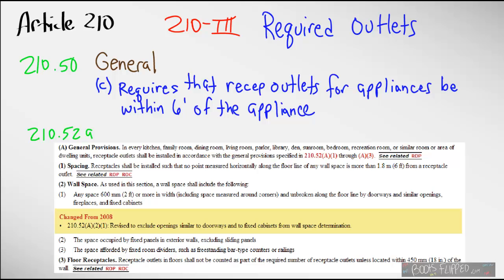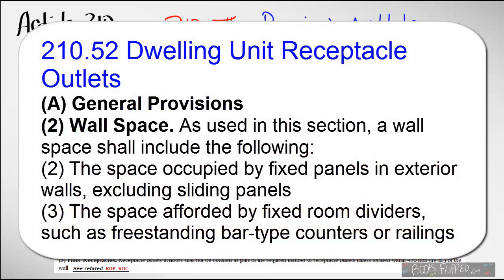Also, this code article lets us know that if there's a fixed panel on the exterior wall, that is included in wall space. Where that comes into play is if you have a French door that has one side that doesn't open, the side that doesn't open is counted as part of the wall. If you have a sliding glass door, the side that doesn't open is counted as part of the wall. The rest of that article or part of the article tells us that the space afforded by fixed room dividers, such as freestanding bar type counters or railings, anything protruding out of the wall that's fixed up to the wall, we have to count as wall space.